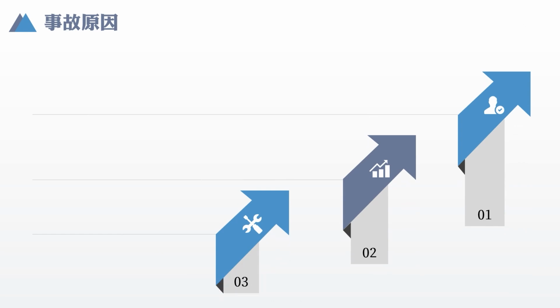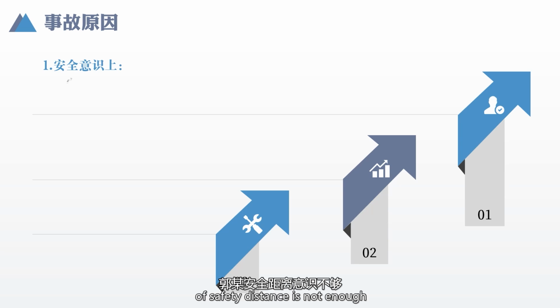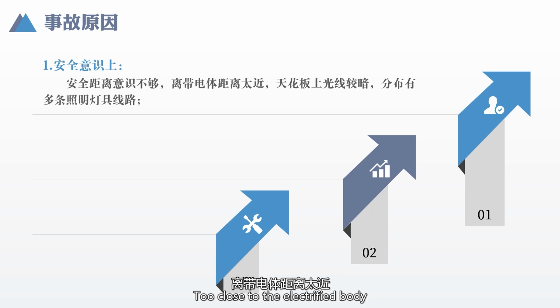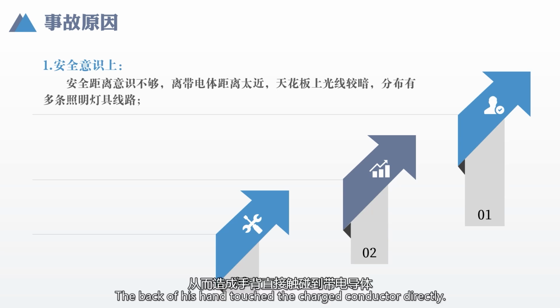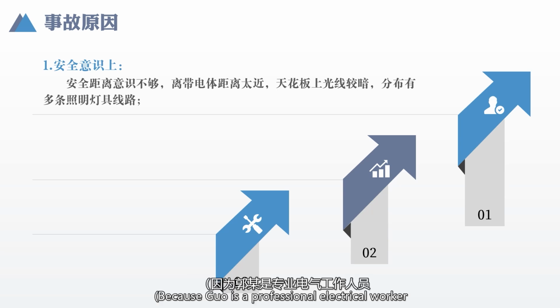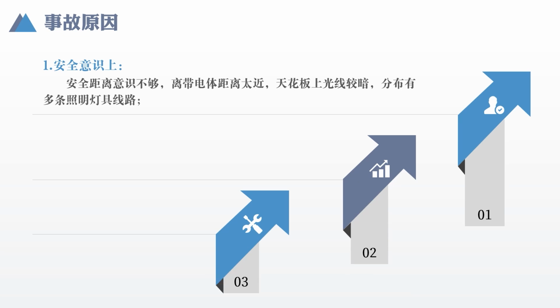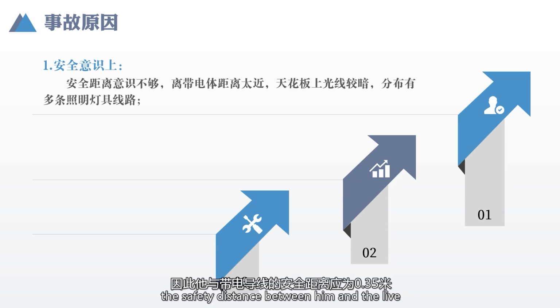We can analyze. Cause 1: from the safety awareness. Guo's awareness of safety distance was not enough, too close to the electrified body. The back of his hand touched the charged conductor directly. Because Guo is a professional electrical worker, the safety distance between him and the live conductor should be 0.35 meters.